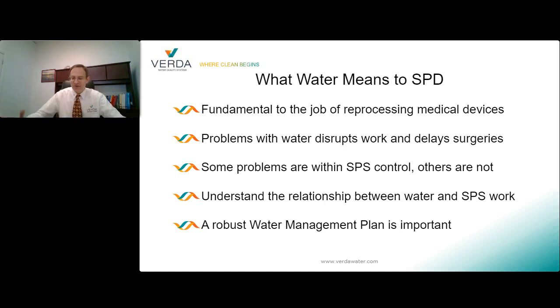Some parameters may vary over the course of the year as seasonal changes impact the water supply, like runoff into the water supply with the springtime thaw, or the municipal water authority changing the actual source of the water during the year. For instance, in the summertime they pull from a different source than in the winter. Knowing the details on changes to the municipal water supply isn't your responsibility, but understanding how the water you use in the SPS impacts the instruments being processed should be.